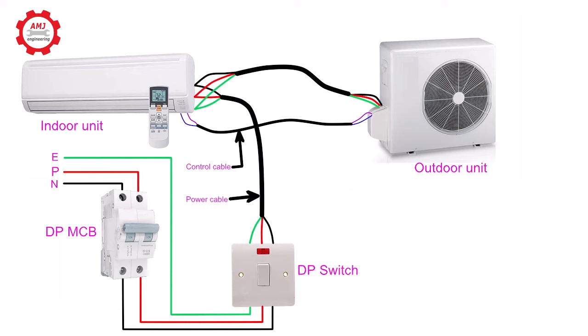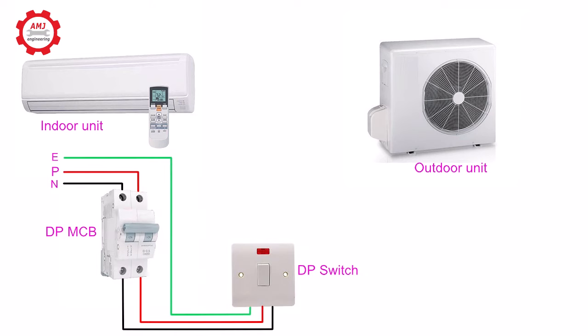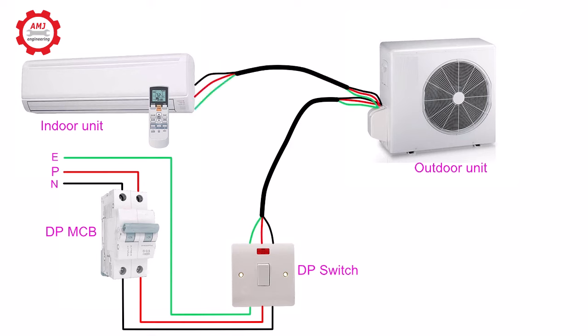That is why it's called indoor fed outdoor. The second one is the connection of split AC where outdoor fed indoor. Here the power lines from the double pole switch first go to the outdoor unit, and then the power supply is given to the indoor unit from the outdoor unit. The rest will be the same.